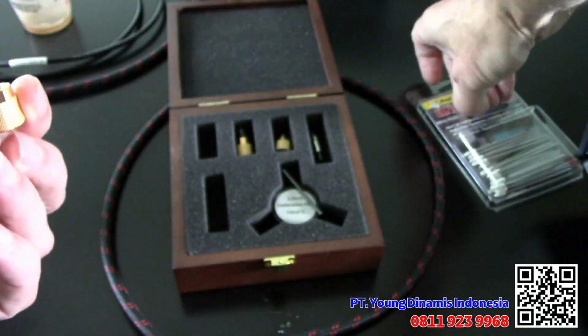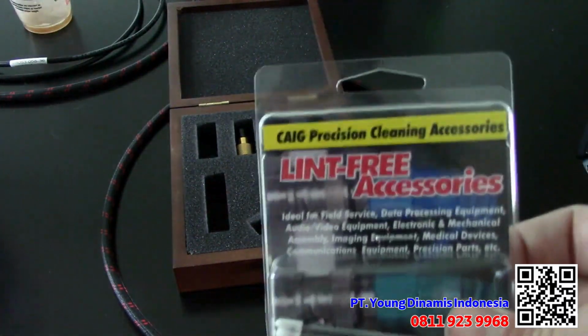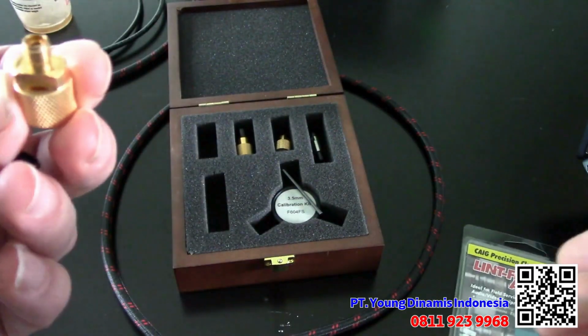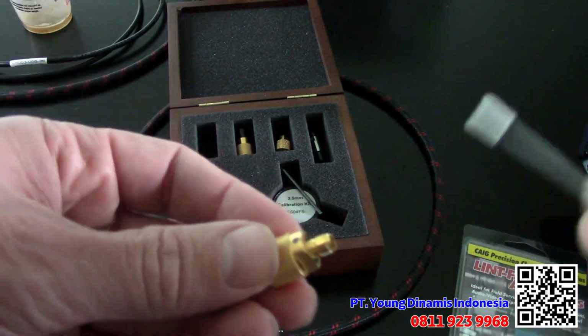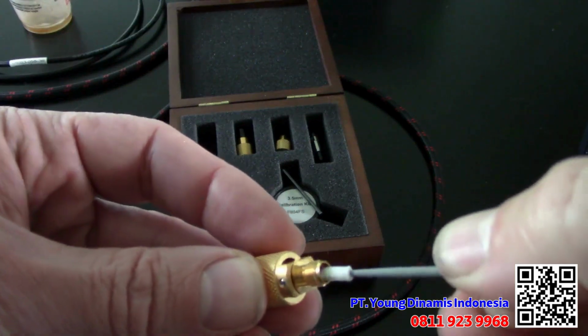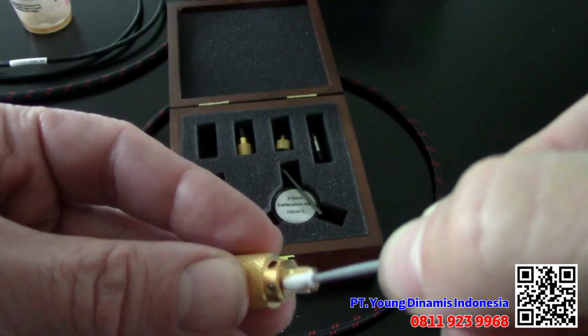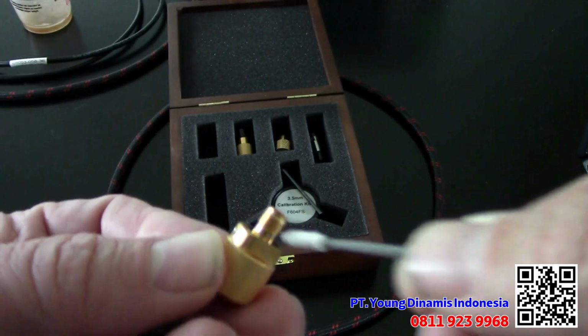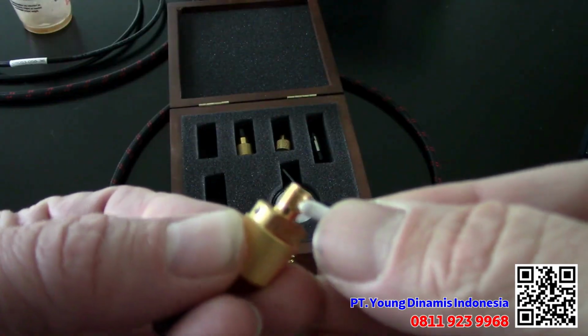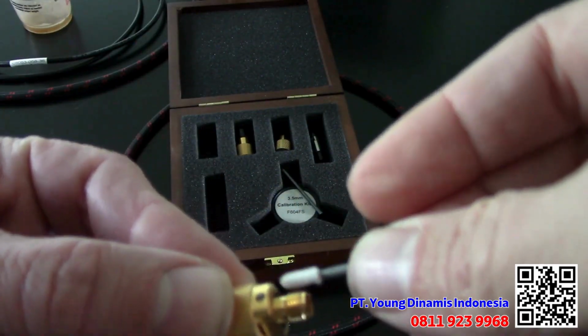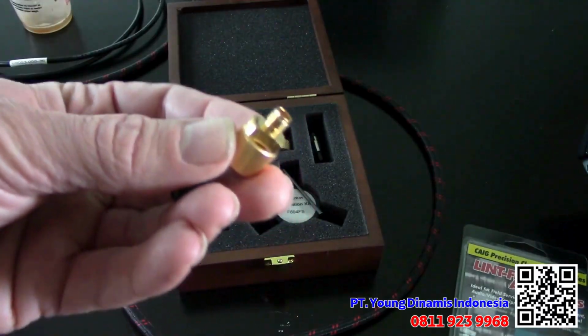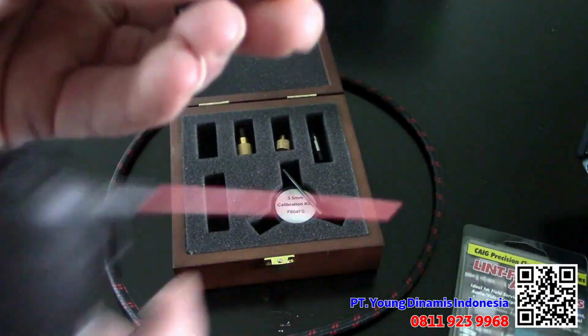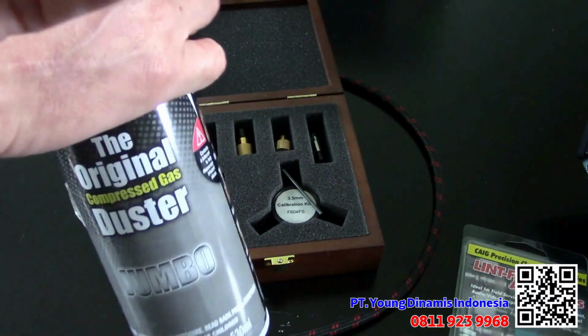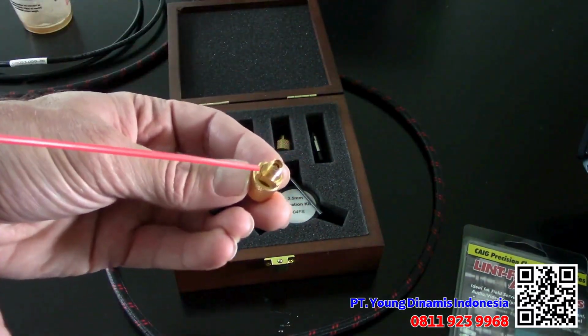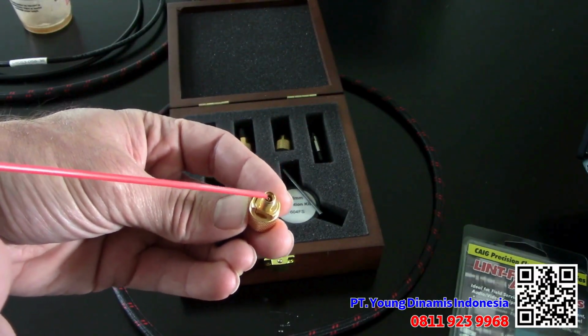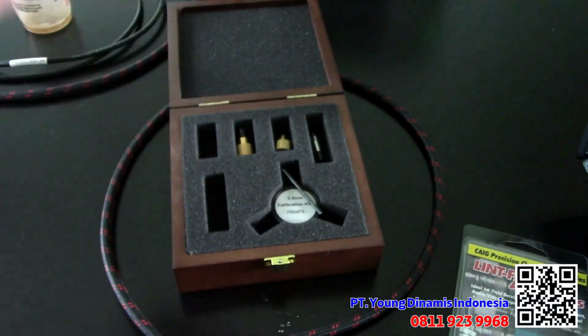Here we've got some lint-free swabs. Unfortunately, I don't have any cloths with me today, but we're going to put some isopropyl alcohol on and we're going to swab around the interior of that connector, that center conductor, and also the threads. We could also use the tip of the swab here to get into the threads, or we could use a lint-free cloth. And after we've cleaned, we can take our compressed air and give that a quick shot just to blow off any of that residue from the IPA, or isopropyl alcohol, and get any dust off of it. Now we can replace the cap if we're not going to use it right away.